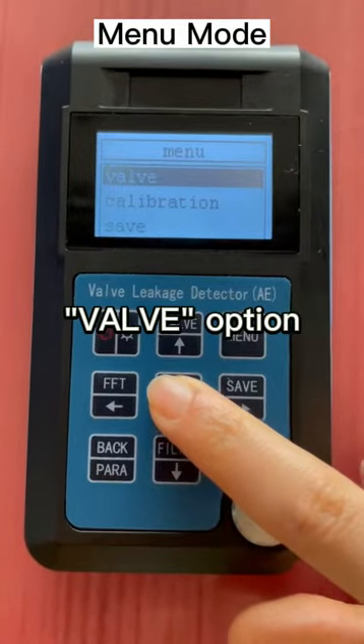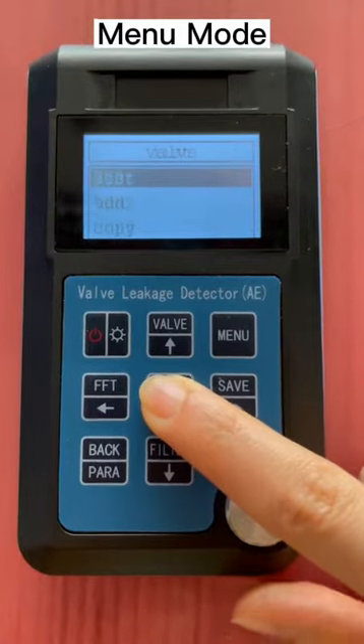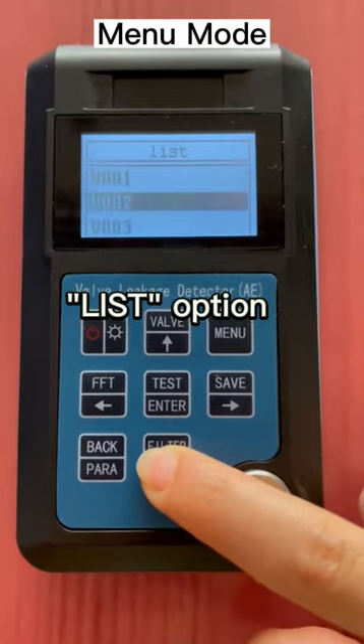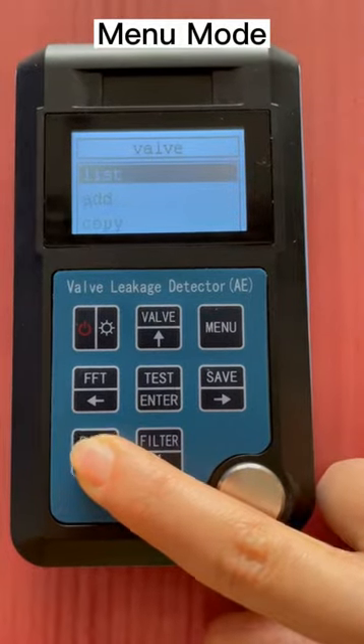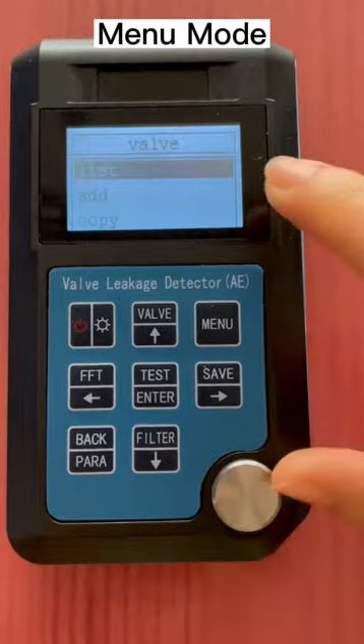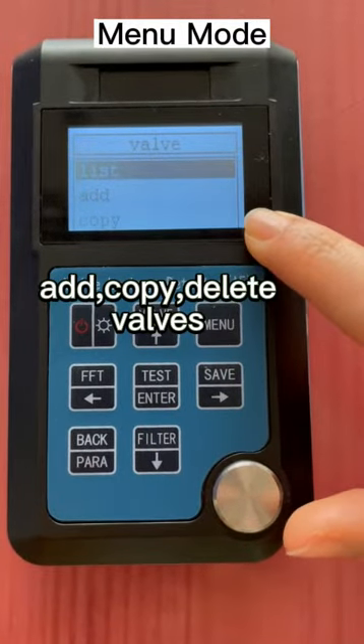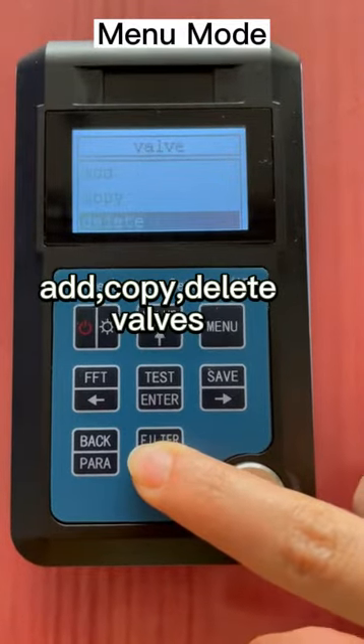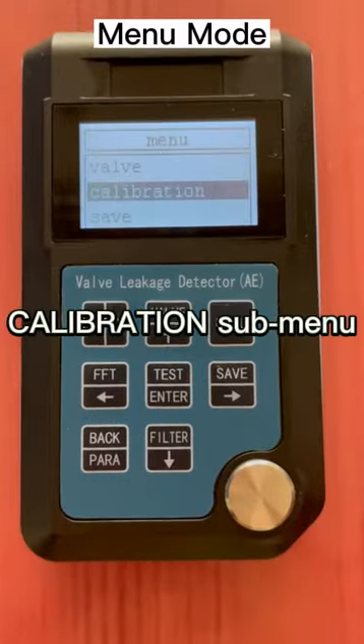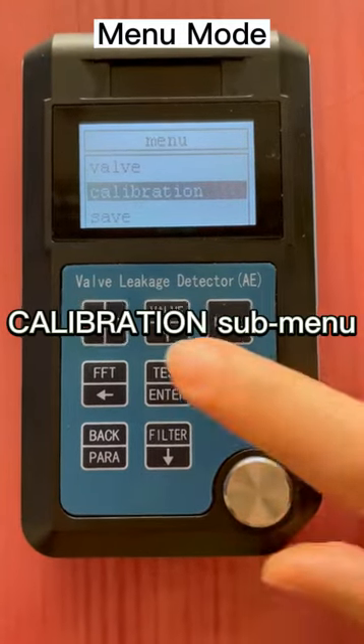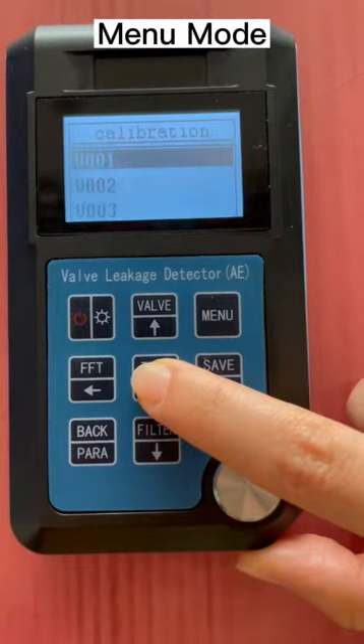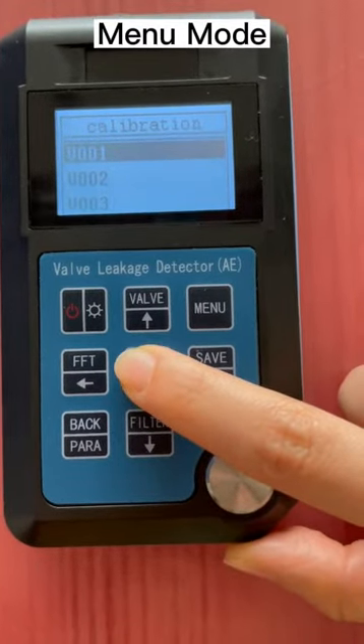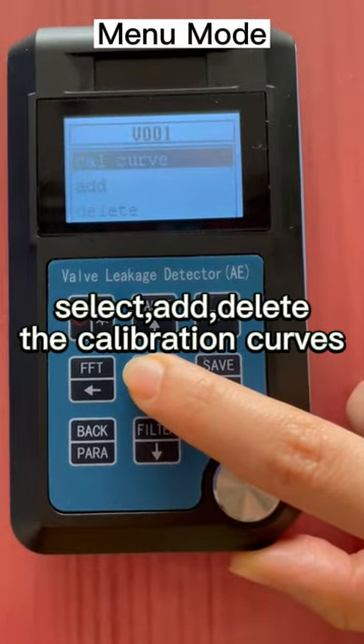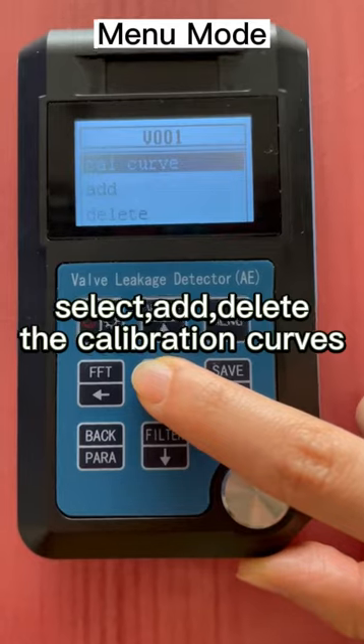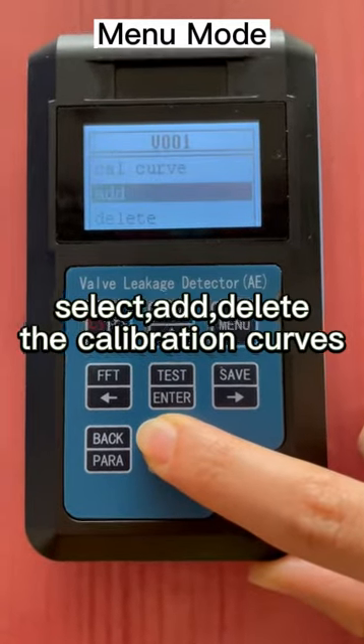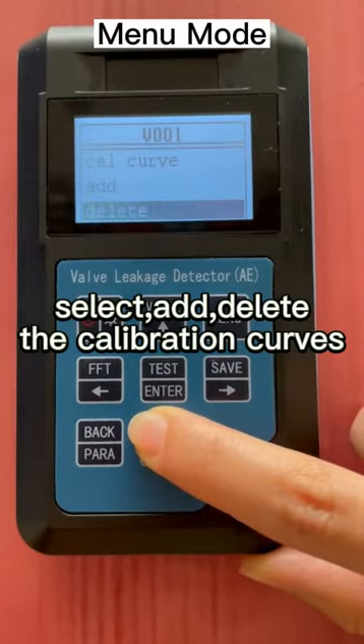Enter the valve menu and select the list option to check all the valves stored in the device. Besides the list option, it also has options to add new valves, copy from the existing valves, and delete the stored valves. In the calibration menu, it first lists all the valves in the device. After selecting one valve, you can select its existing calibration curves to start calibration, add a new calibration curve, or delete the calibration curves.